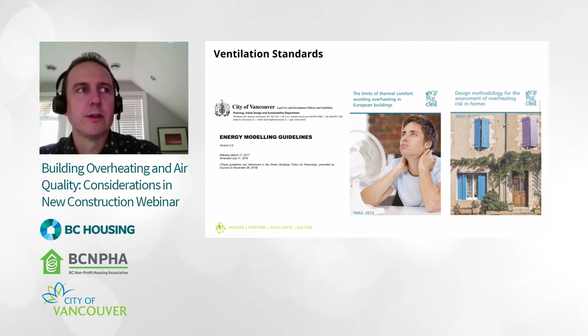An alternative we've found a lot of impact and success with is the Chartered Institute of Building Services Engineers guidelines. These are design methodologies for both non-residential and residential buildings. The residential guideline specifically focuses on maintaining good thermal comfort within bedrooms, since sleep is key to health and well-being, and it's difficult to sleep in a very warm bedroom. It sets limits on maximum temperature, for what percentage of nighttime hours, and an absolute maximum daily temperature for each room. Through energy or thermal comfort modeling, we can model any space to demonstrate whether it meets these guidelines, looking at future climates such as 2050 or 2080, to determine the appropriate solution for good thermal comfort.